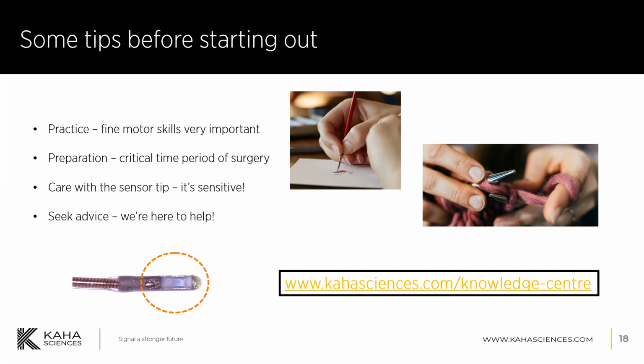As I've already mentioned, the Millar microtip pressure sensor, which is located down here at the catheter tip, provides really great pressure measurements, but it is more sensitive than a fluid-filled catheter. So we really recommend that when you're handling it, you avoid handling the 5 millimeter area right at the tip as much as possible, and don't go anywhere near it with forceps if possible, particularly this white window area, which is where the pressure is detected. We recommend the use of forceps padded with silicone tubing, and that you only handle the wire area of the catheter.